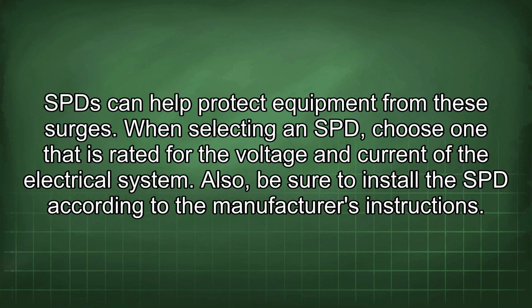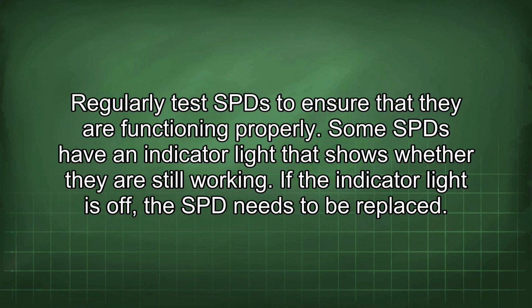When selecting an SPD, choose one that is rated for the voltage and current of the electrical system. Also, be sure to install the SPD according to the manufacturer's instructions. Regularly test SPDs to ensure that they are functioning properly. Some SPDs have an indicator light that shows whether they are still working. If the indicator light is off, the SPD needs to be replaced.